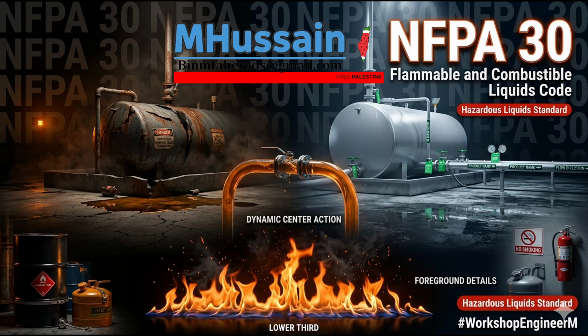And we actually have a true story from our sources that perfectly illustrates what happens when you treat all liquids like they have the same risk profile. Oh, the factory incident, yes. Yeah, so there was this manufacturing factory, and they were storing highly volatile Class I solvents and relatively stable Class II oils right next to each other in the exact same general warehouse space. They didn't establish distinct hazard zoning. Right. The building's ventilation and electrical systems were basically engineered for the baseline hazard of the Class II oils. Which is a classic fatal compounding error. You have a room engineered for a liquid that only off-gases at 120 degrees. Exactly. And then, naturally, a minor leak happens from one of the Class I containers. Since it flashes at room temperature, it instantly starts generating this dense vapor cloud. And the baseline ventilation just couldn't clear it.